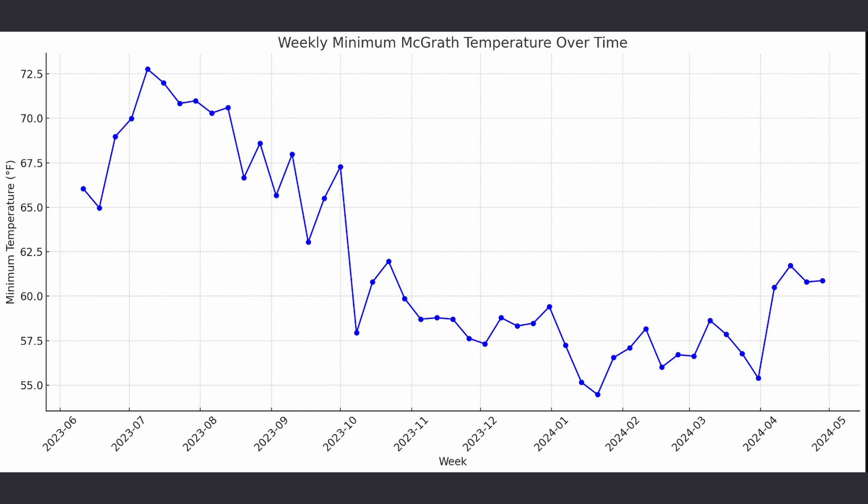This is not a crazy thick wall assembly. We managed to get something like 2 inches of EPS foam behind the pipes, and we sealed the gaps with canned spray foam. I'm sending along a quick graph showing the lowest temperature recorded each week and a pic of the assembly. The data logger will keep recording for about a year and a half and then run out of memory, so we might get one more winter's data set. We should be good until the next ice age.